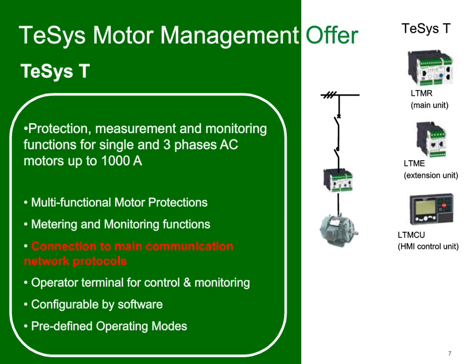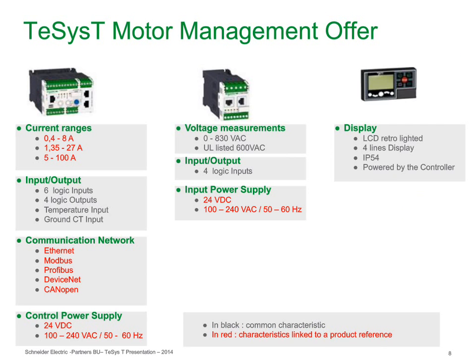We have configuration software to make it easy to set up, and predefined modes of operation that allow you to use standard setups for most of your applications. This slide's a little technical, but again, I want to show you the great capabilities of the product. There's 3 different sizes of current ranges that go through 8 amps, 27 amps, or 100 amps, where we run wires right through the current transformers in the unit. We can go to much, much higher amperages, up to 1,000 amps. In those cases, we'd use external CTs.